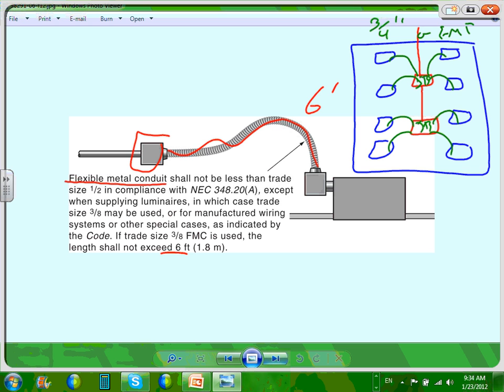You can go as low as a smaller 1/2 inch or 3/8 even for pre-manufactured wires. But for the most part, 1/2 inch, and you go with 2 wires, bam, bam, to every single fixture. A lot of fixtures come with a pre-manufactured fixture whip and 2 wires coming out of it, and you just tie it with 6 feet to your box. What's the advantage? Ease of installation of these systems.